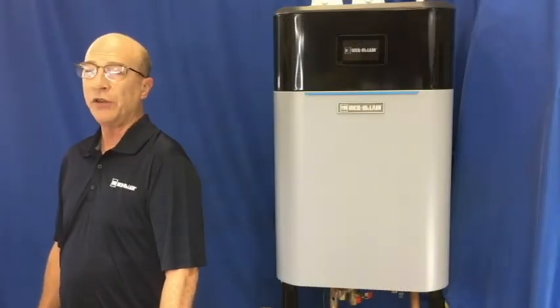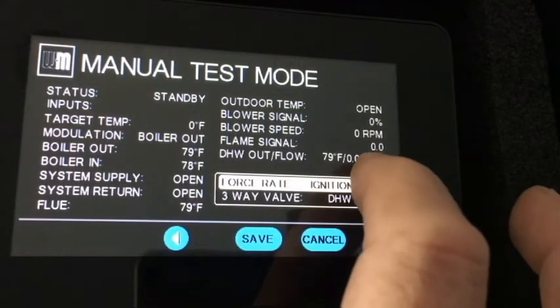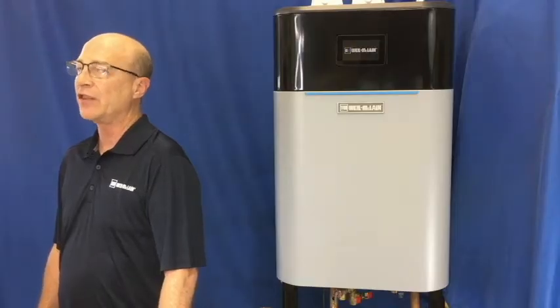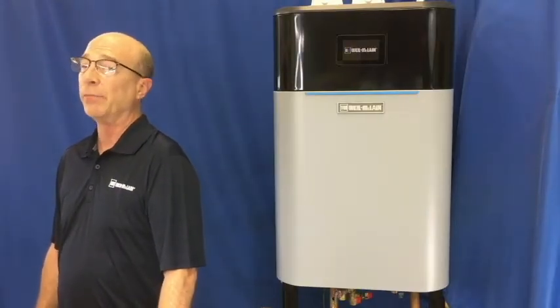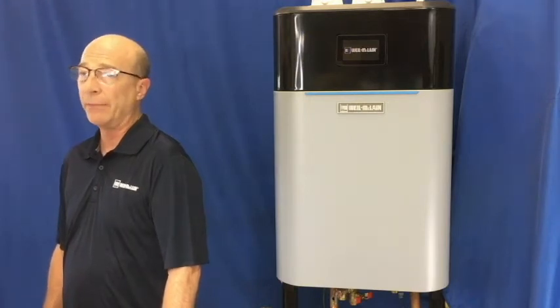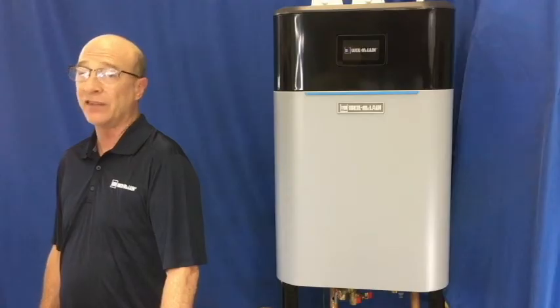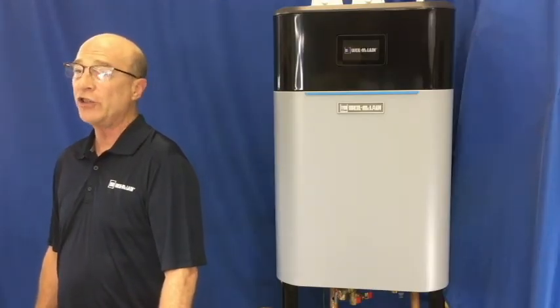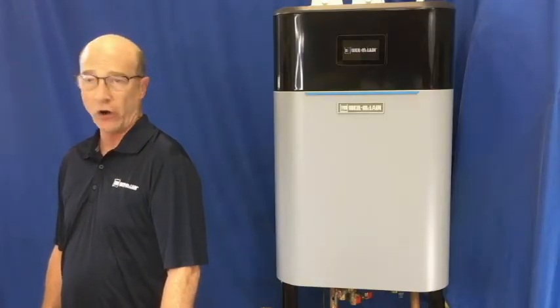It should be below the maximum CO. Now, put the unit back in high fire, recheck the CO2, and observe the CO. It should also be below the maximum listed in the chart. Remember, the carbon monoxide is a maximum level — it is not a target. So as long as you are anywhere below that number, you're all set.